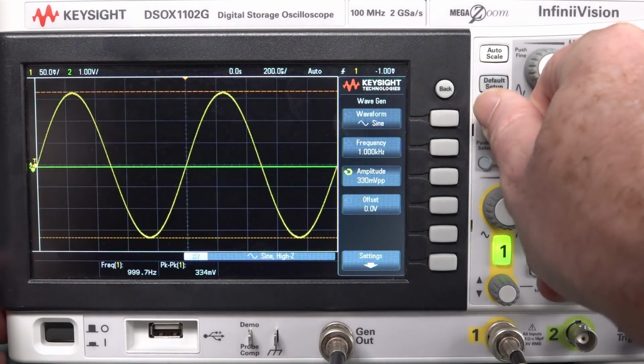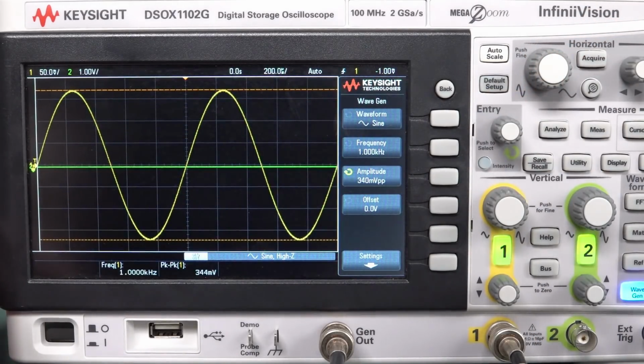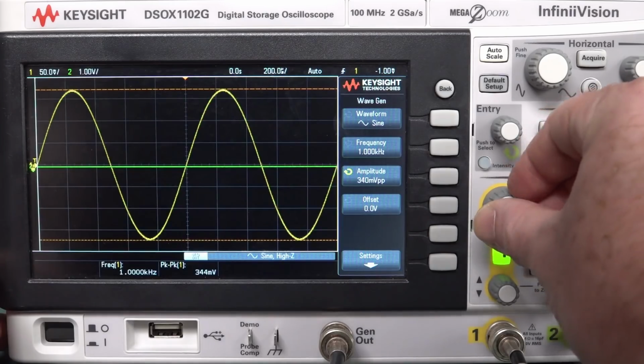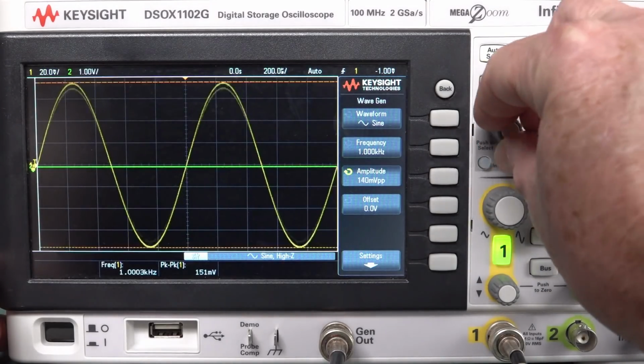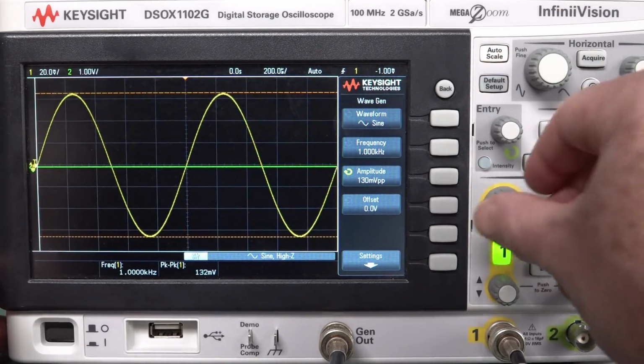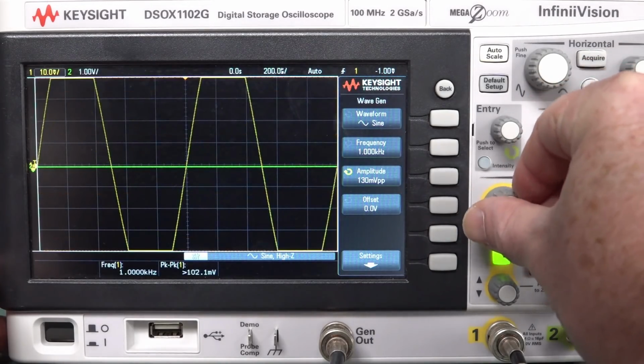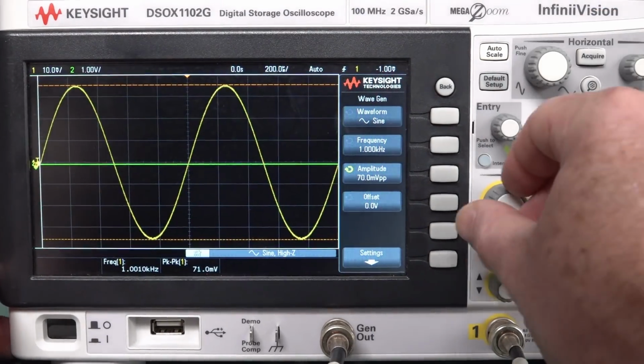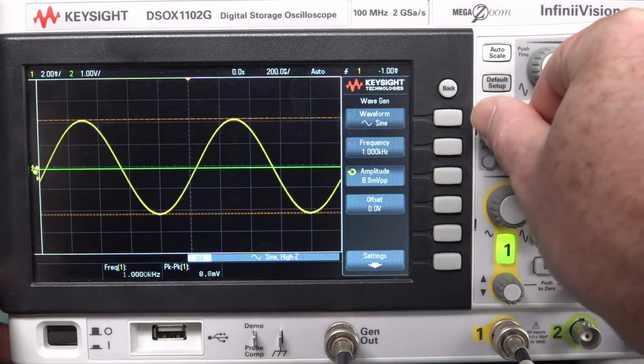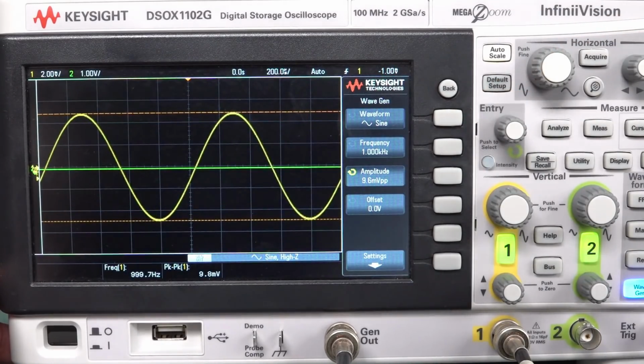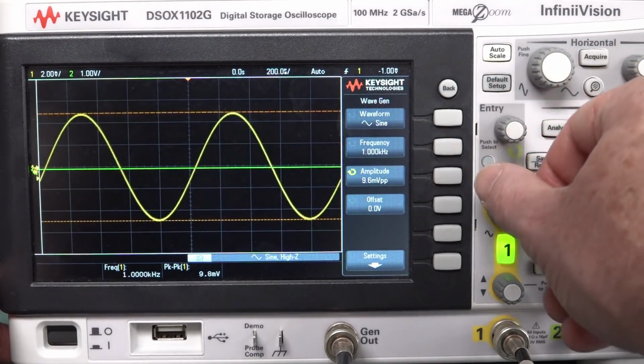So yes, I know that the calibration could have screwed up the WaveGen as well, but it's unlikely that both of them are out by the same amount. So I can double check with another scope or another function gen, of course. No, I'm fairly confident that this is actually okay. Yep, 70 millivolts, no worries. Even down to the smallest signal levels, 9.6, we're measuring 9.8, no worries.